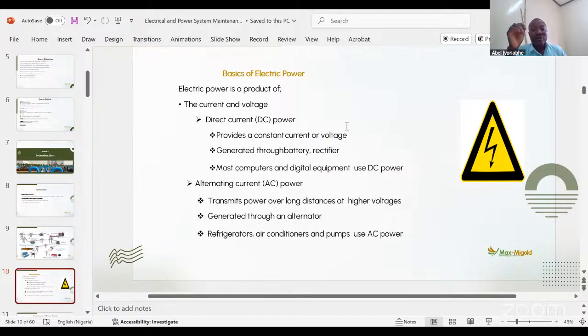So we have direct current. Direct current is what you produce from your battery. An alternating current can also be rectified to a direct current through a diode or a rectifier. That's why in your generator you have a rectifier, a diode. They call it a rotating diode that gives constant supply to your battery and to your charging system. If they are bad, your generator will be shutting down. I know many people have come across the rotating diode.